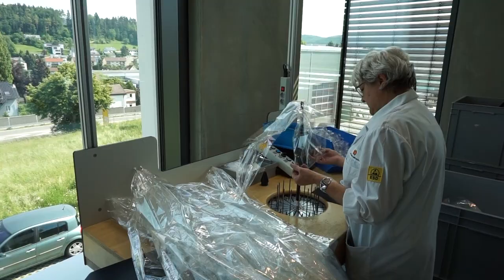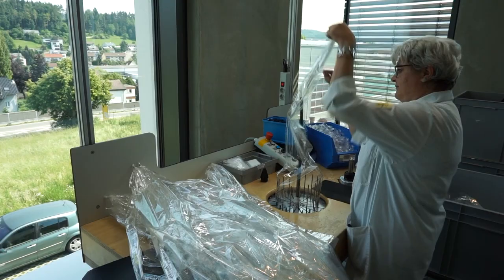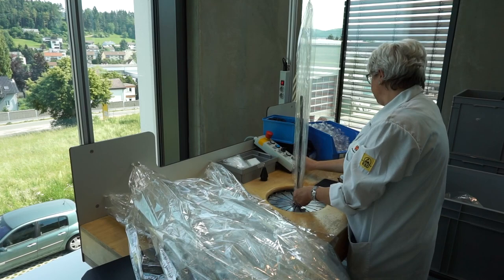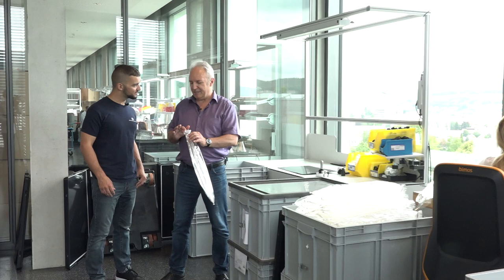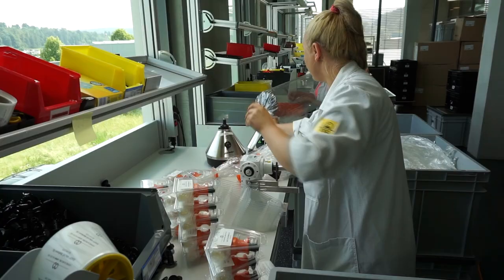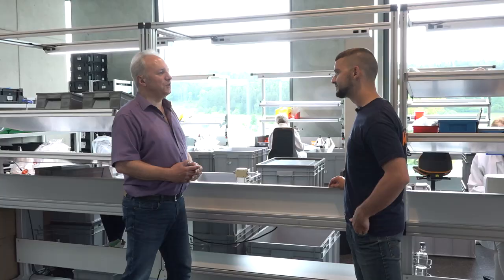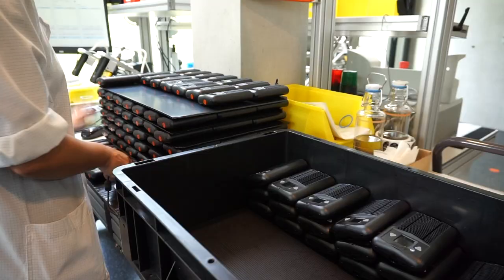Here we are doing the assembly of our easy valve balloons. Before, we made them by hand, but then we had to develop machines to do the job. This is one such machine — they are the only machines we have in our factory, as all other parts are already machined by our suppliers. Nobody was able to deliver such balloons, so we had to figure out how to make them ourselves. This machine gives 16 perfect folds to the inner ring. We had it designed specifically for this purpose. The balloons are assembled, packaged, and tested here — every tenth balloon is blown up to check whether it is airtight. We have a lot of quality controls, not only for incoming parts, but also during and after production, and of course there is a final control.